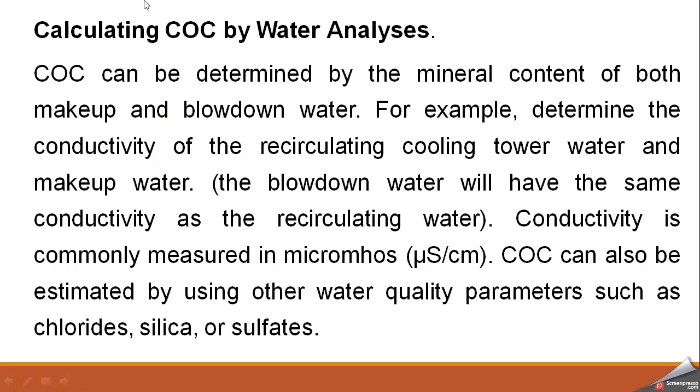Now, COC can also be calculated with the help of water analysis. COC can be determined by the mineral content of both makeup and blow down water. We analyze both waters and then, for example, determine the conductivity of the recirculating cooling tower water and makeup water. The blow down water will have the same conductivity as the recirculating water, because we blow down or discard the water which is present in the cooling tower. That's why the chemistry of blow down water and cooling tower water are the same.